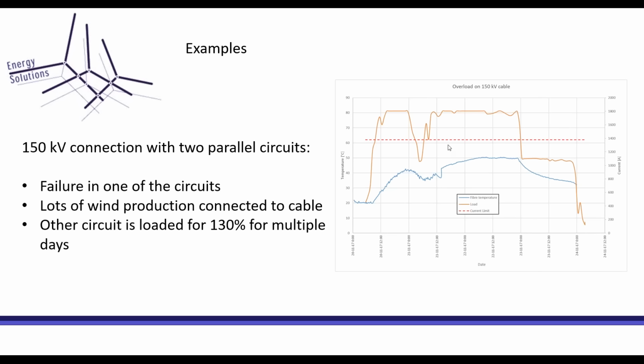And what you can see is that there is still a lot of room in temperature. The maximum fiber temperature for this cable was about 50 degrees, which in this case represents a maximum of about 70 degrees conductor temperature. And 90 degrees was the limit for this cable. And you can see that the load was for multiple days above the continuous rating. And because of the large time constant of the cable, it was not a problem to overload this cable this much.